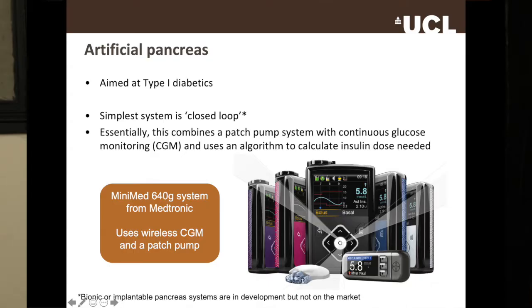What you really want is something like an artificial pancreas, shown on screen. Artificial pancreases are aimed at type 1 diabetics really, because they need long-term replacement of a pancreas. In that system it's essentially a patch pump, but the software uses artificial intelligence and measures blood glucose levels directly in order to work out autonomously when to inject insulin. It's essentially a patch pump combined with a glucose monitor, with software taking blood glucose readings and automatically directing the pump to add insulin as necessary.